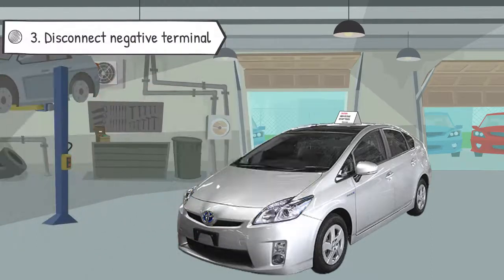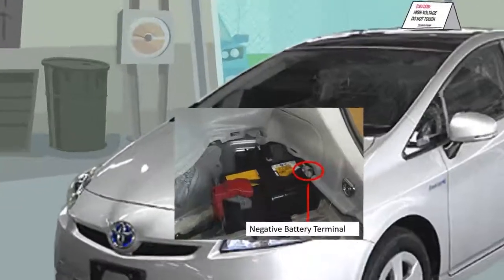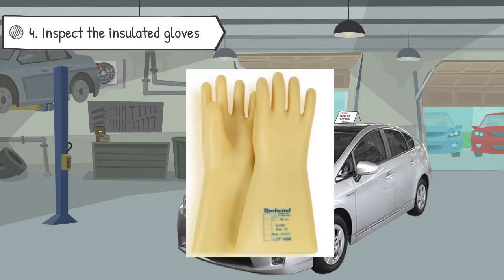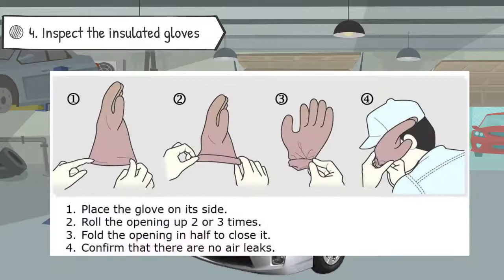In third step, disconnect the negative terminal from 12-volt auxiliary battery. In fourth step, inspect the insulated glove before use. Be sure to check them for cracks, tears, and other types of damages. Then perform the following procedure to inspect air leak. First, place the glove on its side. Second, roll the opening up 2 or 3 times. Third, fold the opening in half to close it. Confirm that there are no air leaks.